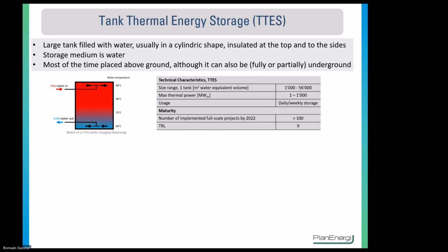Some overall general technical characteristics. So usually the volume can be between 1,000 and 56,000, or that's at least the maximum so far, cubic meters of water. And the max thermal power can range from 1 to 1,000 megawatts thermal. And this basically depends on the size of the pipes and the diffusers, but the range is quite wide. It's usually used for daily or weekly storage, considering the relatively small size of the storage. And it's a very mature technology, with many implemented projects listed.